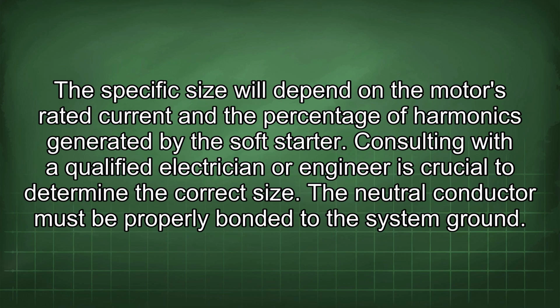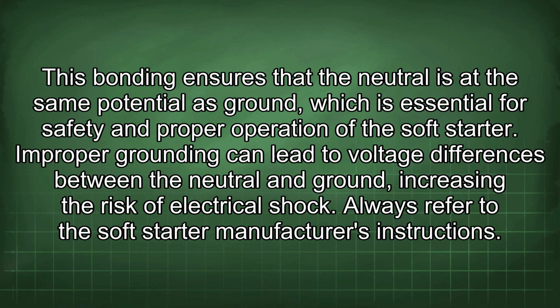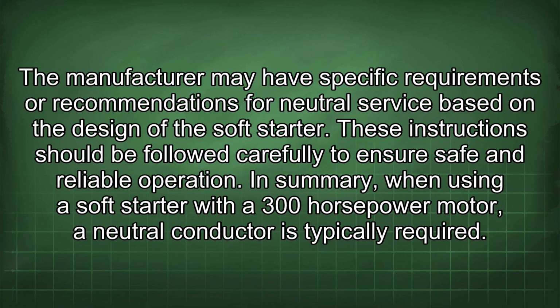The specific size will depend on the motor's rated current and the percentage of harmonics generated by the soft starter. Consulting with a qualified electrician or engineer is crucial to determine the correct size. The neutral conductor must be properly bonded to the system ground. This bonding ensures that the neutral is at the same potential as ground, which is essential for safety and proper operation of the soft starter. Improper grounding can lead to voltage differences between the neutral and ground, increasing the risk of electrical shock. Always refer to the soft starter manufacturer's instructions. The manufacturer may have specific requirements or recommendations for neutral service based on the design of the soft starter. These instructions should be followed carefully to ensure safe and reliable operation.